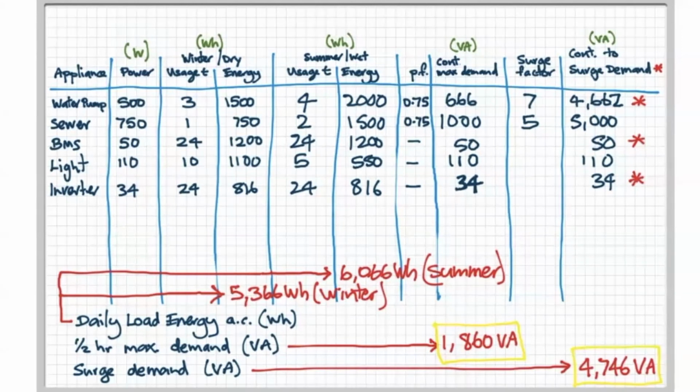So what you're looking at here is a table that I've drawn up. Now this table is actually from Appendix A of AS/NZS 4509.2. Now Rachel will probably put that in the caption. That's the standalone power system design standard for Australia and New Zealand. It was last published in 2009 and 2010, 9 for install and 10 for design. It's a very useful standard, but it's got like an engineering grade calculation. So something like 16 pages of formulas.